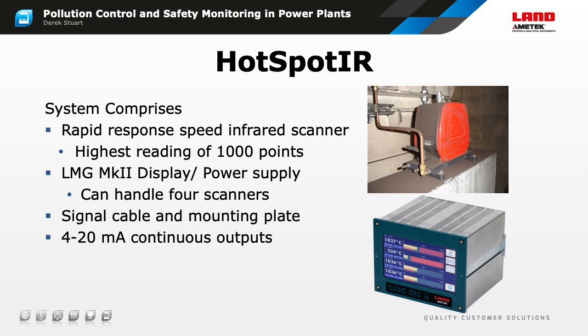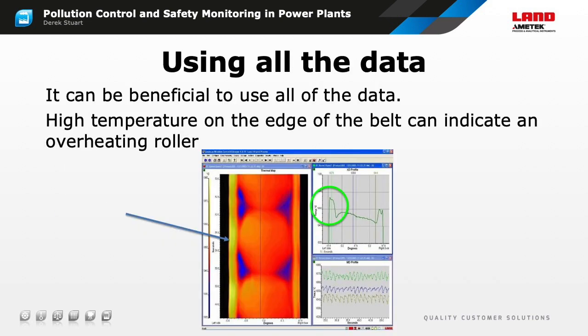A simple processing scheme indicates the peak temperature from each scan as a 4 to 20 milliamp signal, along with a relay which indicates that the peak is above an alarm temperature. The new AMETEK Land LMG Mark II processor allows up to 4 separate scanners to be connected to a single display. We can also choose to use a full graphical display with image processing facilities similar to those of a thermal imager. A peak-picking processor can detect a hotspot.